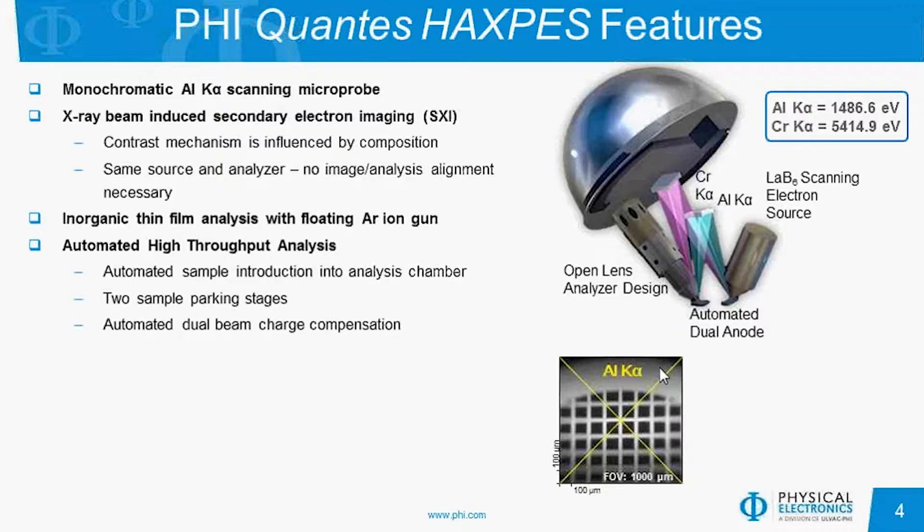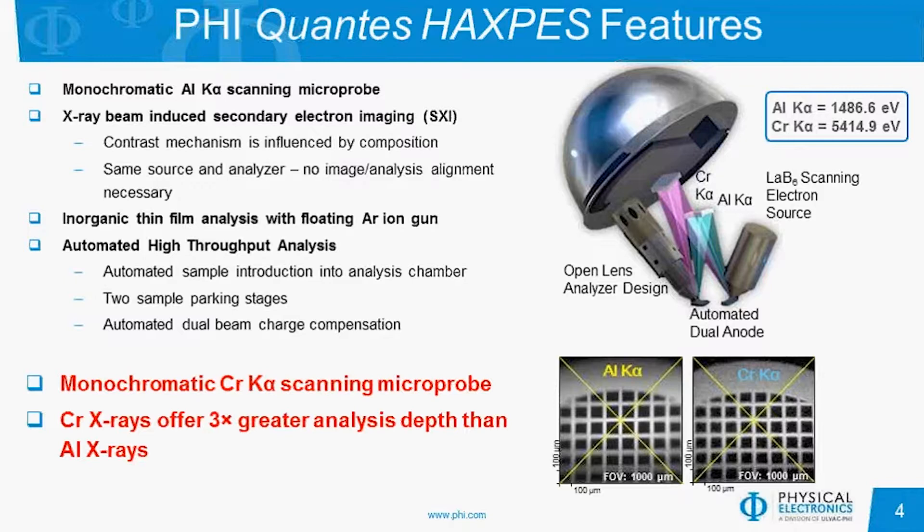In addition, both instruments are equipped with a floating monoatomic argon gun for inorganic thin film analysis, and both instruments have high throughput analysis. For example, there is automated sample introduction into the analysis chamber, two ultra-high vacuum parking locations, and automated dual-beam charge compensation for studying insulating samples. All of these features are the same technology as the Quantera II platform, but the difference in the QUANTES is that it has an additional hard X-ray source.